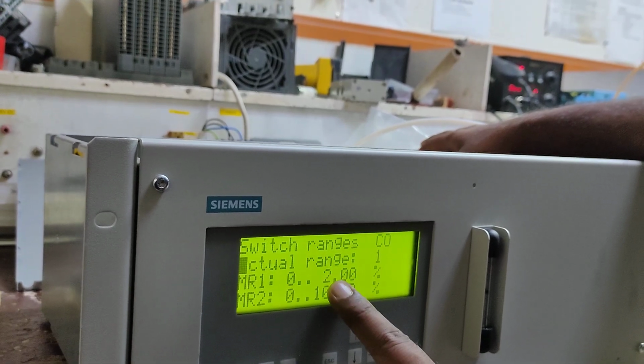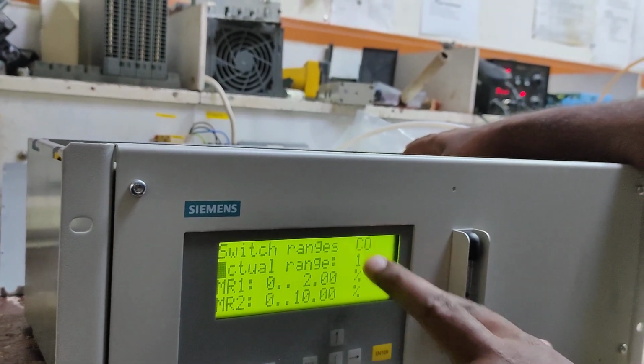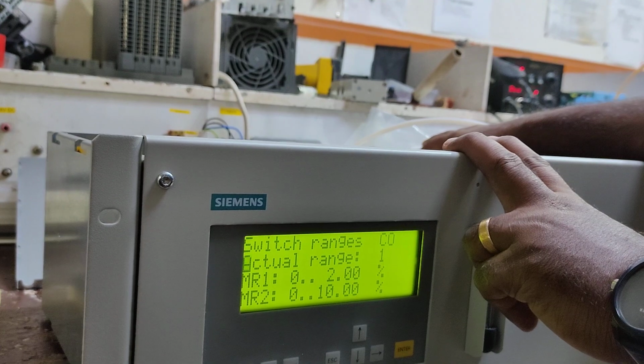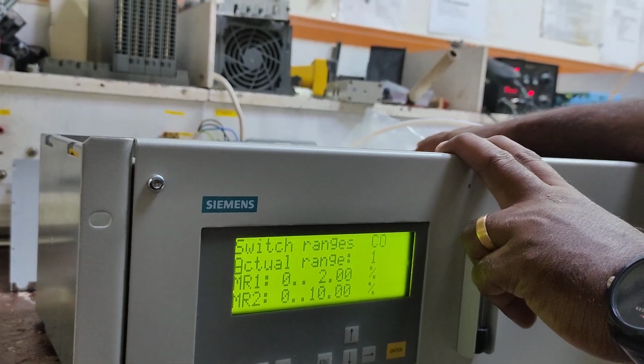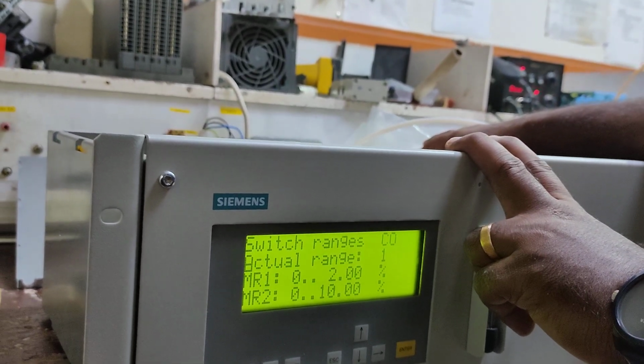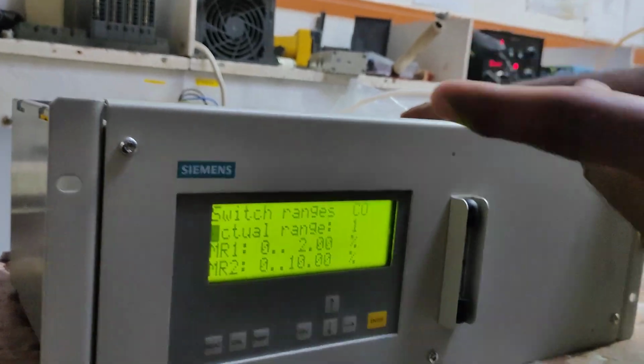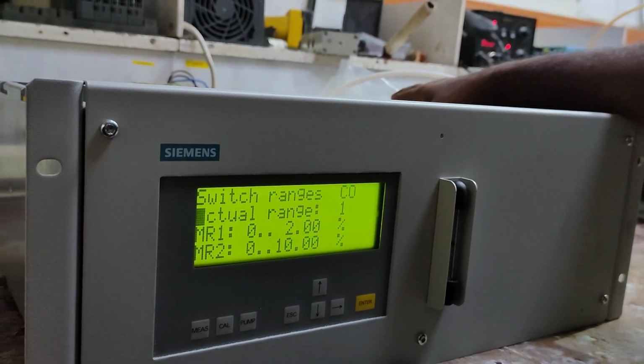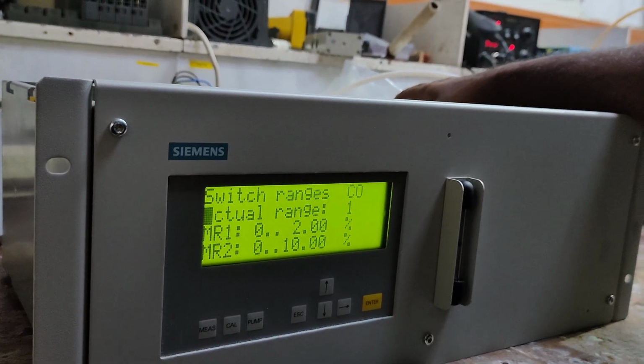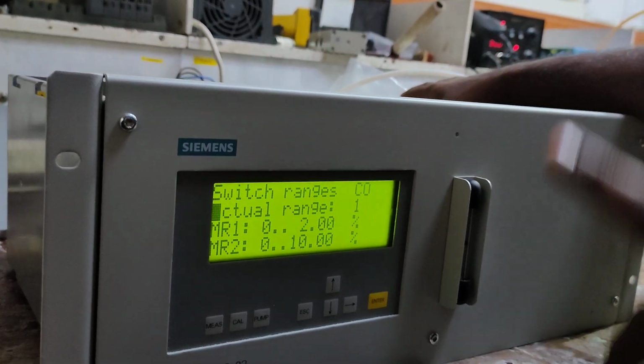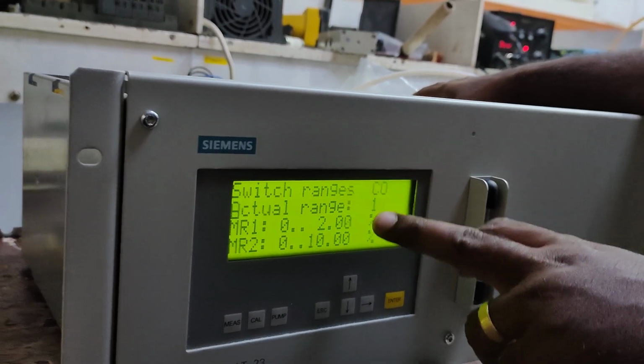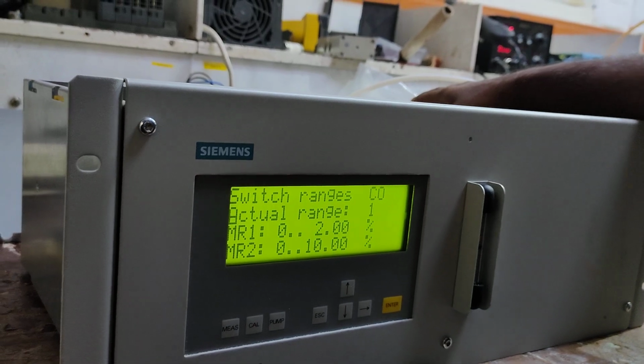How much is the scale? They have set up two ranges: one is 0 to 2%, one is 0 to 10%. With the switch range, what will happen if it reaches around 1.8%? It will automatically change the loop current to 0 to 10%. We don't want that to happen. If it goes more than 2%, it should show over range.